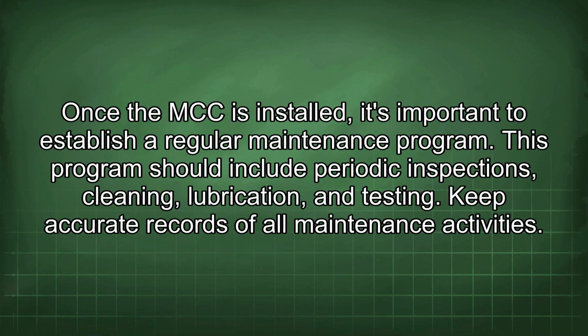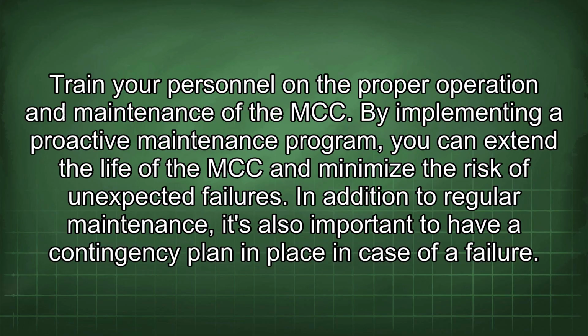Once the MCC is installed, it's important to establish a regular maintenance program. This program should include periodic inspections, cleaning, lubrication, and testing. Keep accurate records of all maintenance activities. Train your personnel on the proper operation and maintenance of the MCC. By implementing a proactive maintenance program, you can extend the life of the MCC and minimize the risk of unexpected failures.